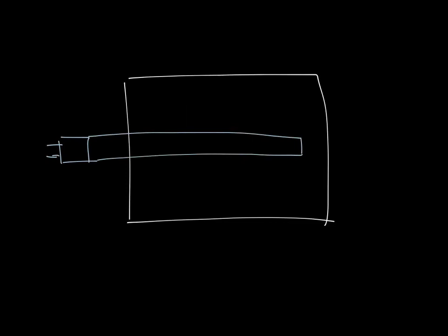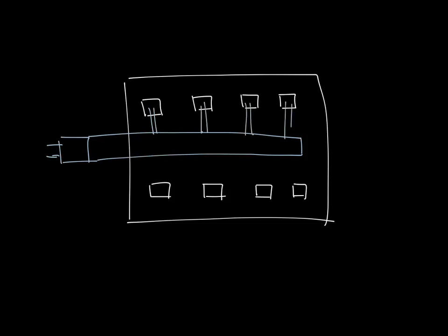While that's part of it, what really sets how many diffusers you put on a VAV box is really about your zone layout. So let's say you have one big zone, like a conference room, and you have one 2000 CFM VAV box supplying the space. Then you can put 8 250 CFM diffusers on it if you want. And this is actually a pretty common layout.